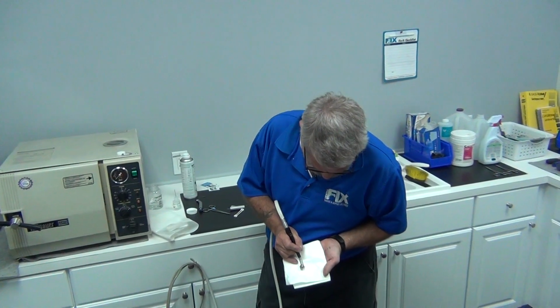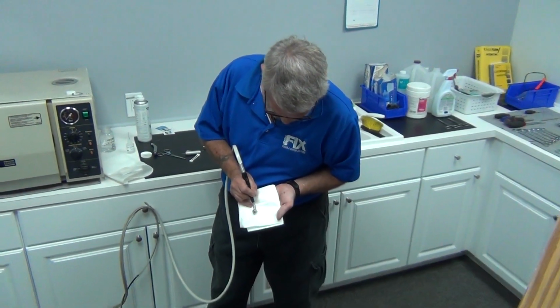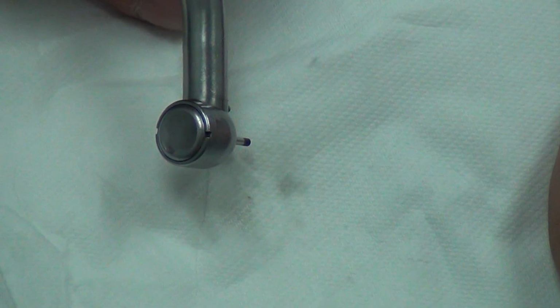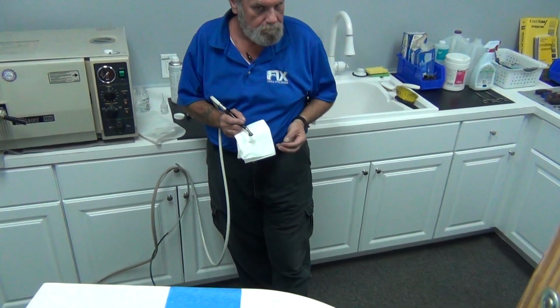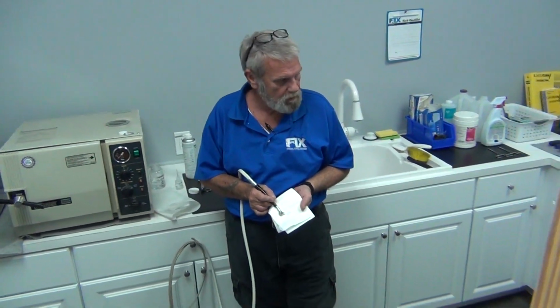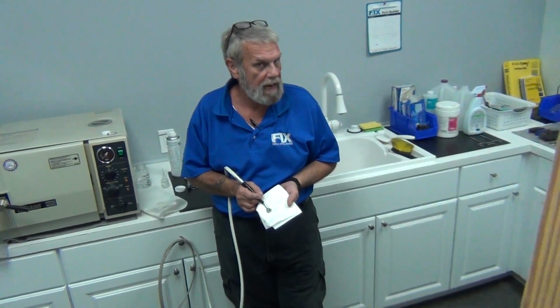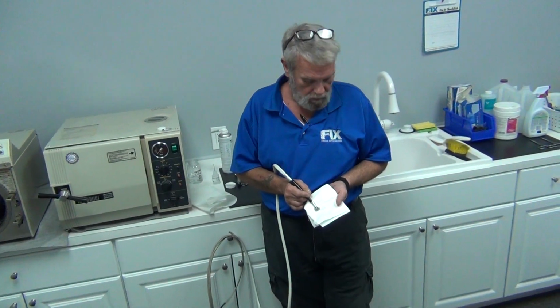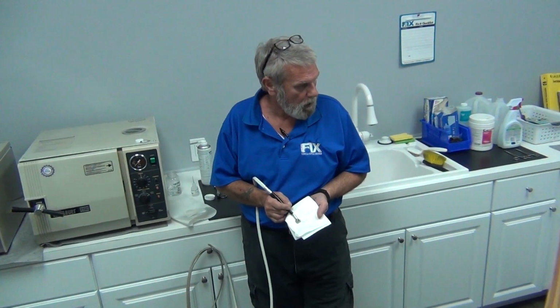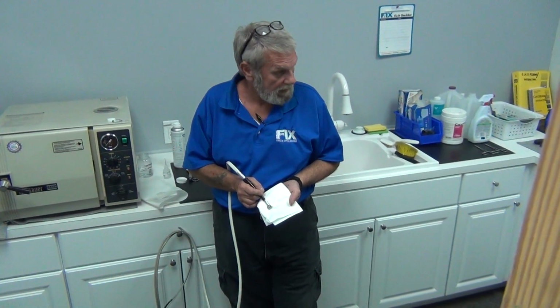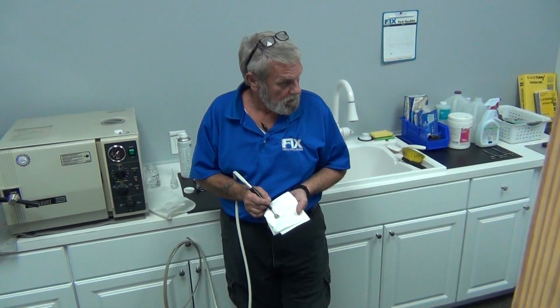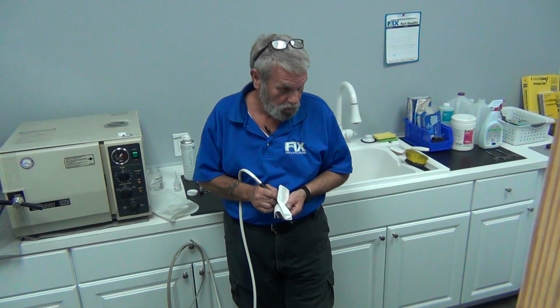Purge again. Oh my goodness. We're still getting debris. Yep. Look at the debris that comes out of it. Purging is very important. This debris, if this doctor's cleaning handpieces, let's say 20 times a day, and he's doing it in a delivery system, that's 20 times that crapola is getting into a delivery system and absolutely ruining the delivery system. Making the tubings hard and brittle, building up in the bottom of the delivery system, has a chance to leak down on a patient. The oil does. Doctor, you have an unsatisfied patient when oil leaks down on a patient.